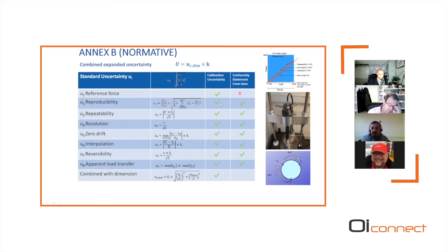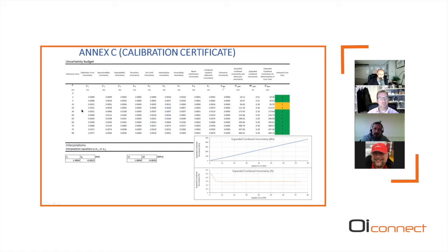And here you see the equations, and there are two aspects. One is for the calibration certificate, where you need to include the calculation of the 8 components, including the dimension, which is a 9th component. And for the conformity statement for cone class, we include all of those parts for the reference force and the dimensional uncertainty. That's for classification of the cone as class 1, 2, 3, or 1 plus. We are also intending to provide an example calibration certificate, again to ensure that every manufacturer and every operator presents the same data sets, and everyone in the industry gets used to seeing the results from a calibration certificate.